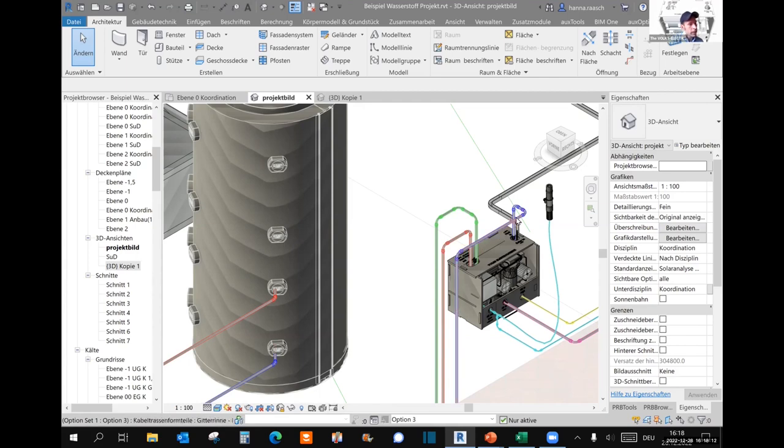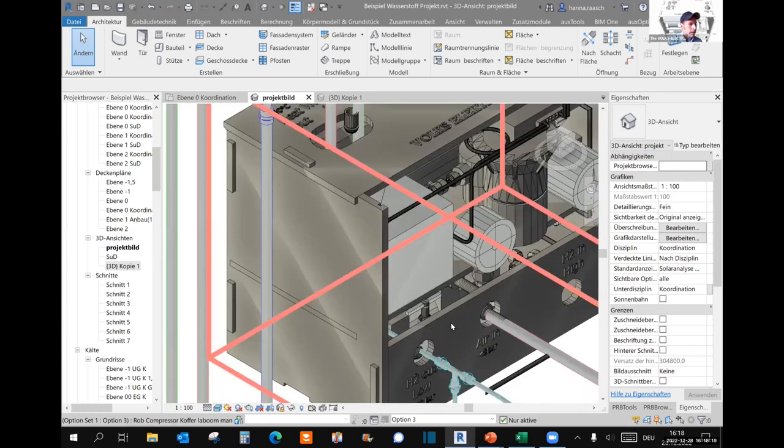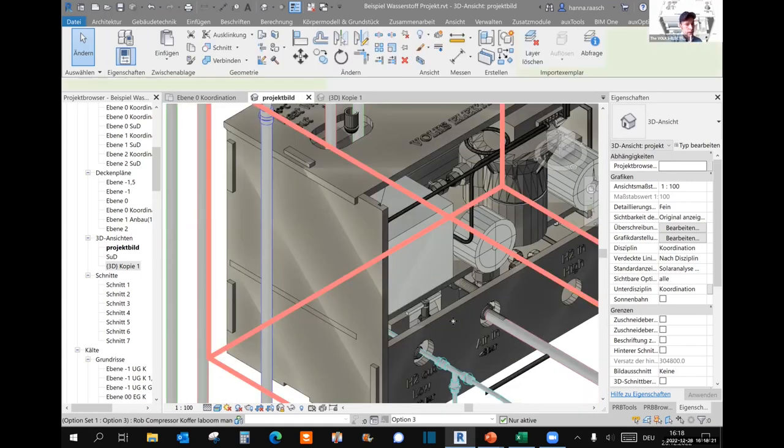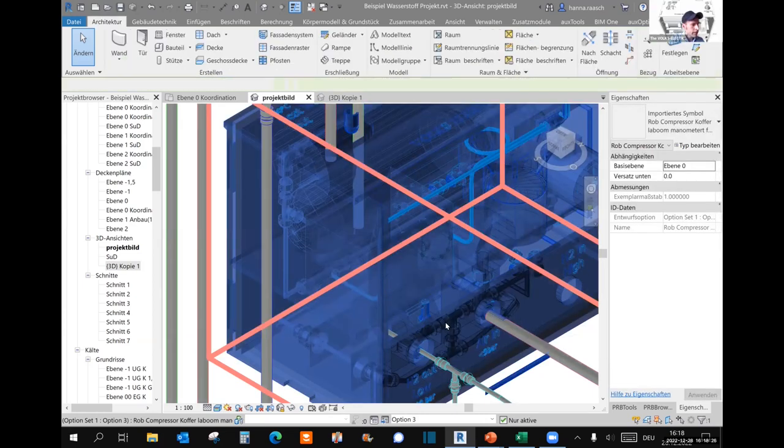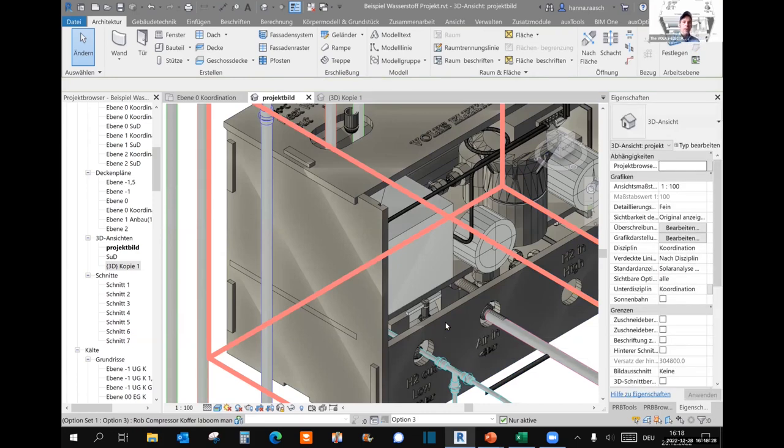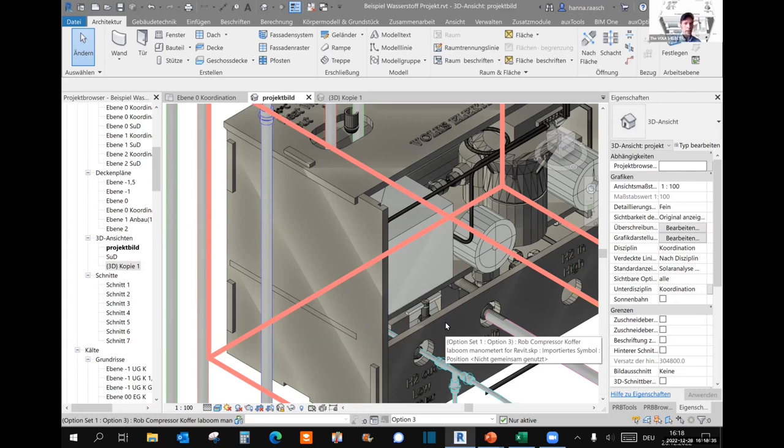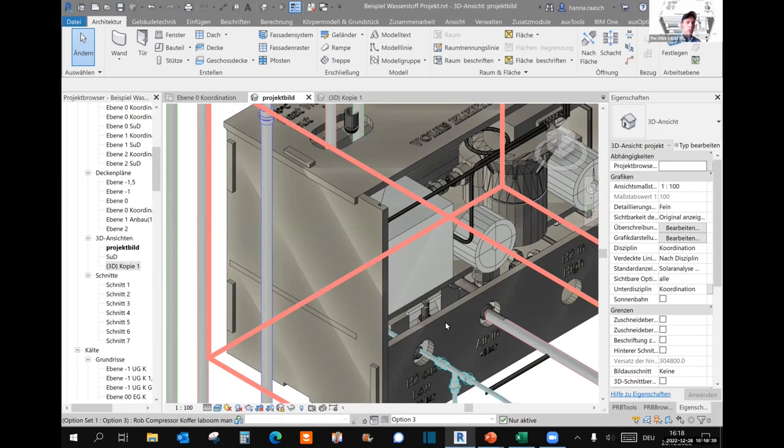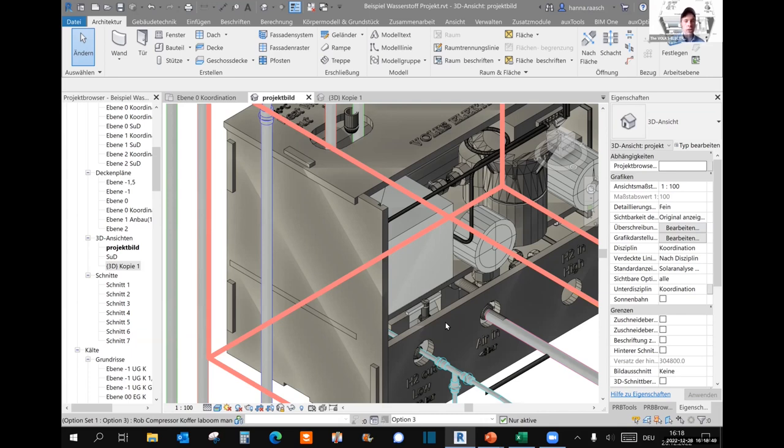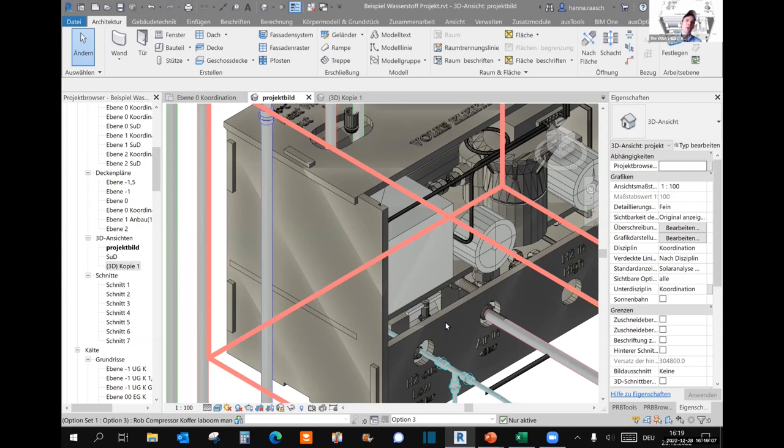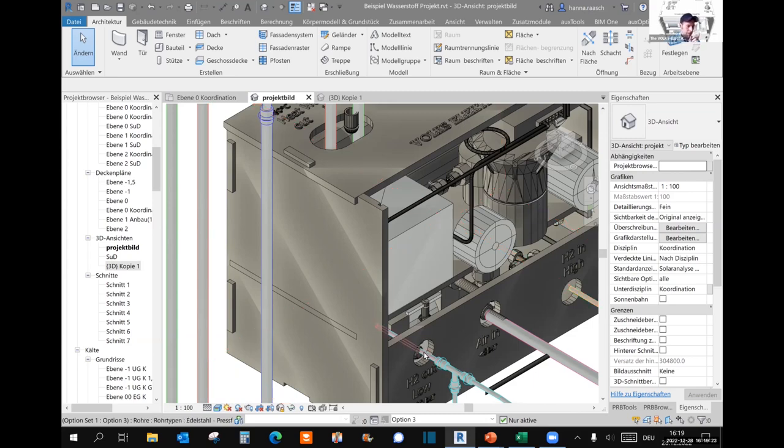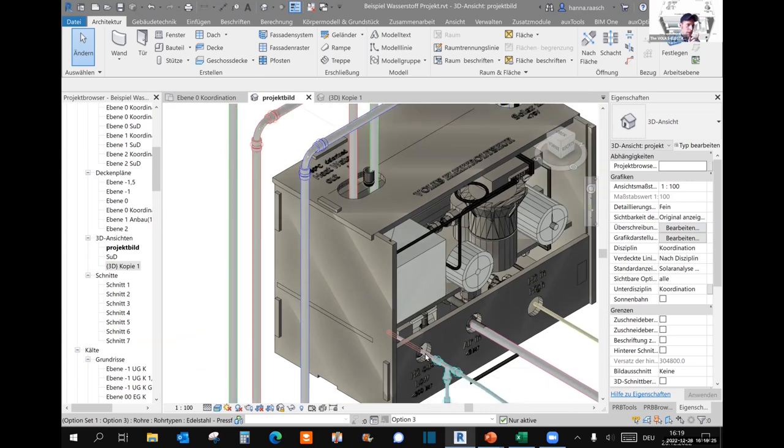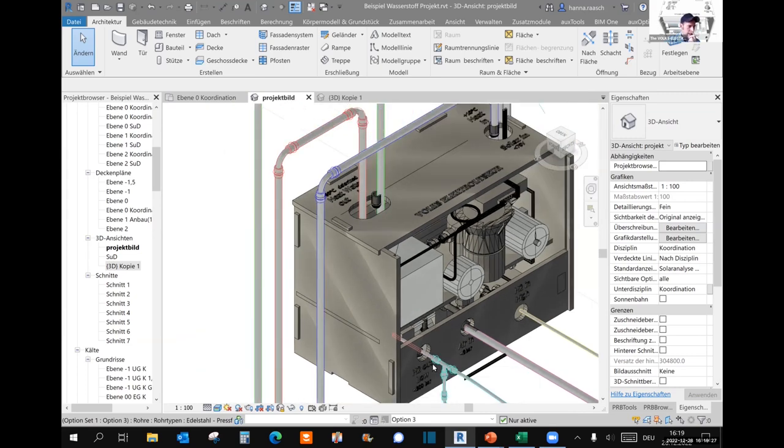I would suggest to insert the electrolyzer waste heat to the bottom because we want the return to be as cold as possible. Beneath the electrolyzer there is the booster, and the booster compresses the hydrogen. Everybody knows that if you compress hydrogen there will be heat. We want the hydrogen to be as cool as possible when it comes into the booster because we don't want the hydrogen to get more than 100 degrees Celsius. This is not only lowering the risk, it is also for the gaskets. The PTFE gaskets in this booster shouldn't get very warm because plastics don't like heat.